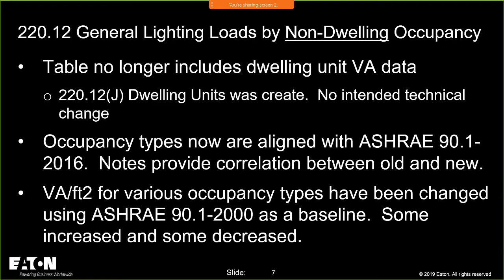The argument that was made was that we're designing buildings to meet these new ASHRAE requirements, which have limitations in watts per square foot that you're allowed to have in a facility to meet those requirements. Now, a key thing that I said there was watts per square foot. What we learned in our task group, in fact, I had one of the members call me Mr. VA, because I kept reminding everybody that when we size equipment, we don't use watts per square foot. But ASHRAE and those energy code guys love to use watts per square foot. And the reason is because we always relate that to our energy bills. We pay for watts. We don't necessarily pay for VA, unless you're in those large commercials where you get penalized for power factor. And that gets you your VA bills.